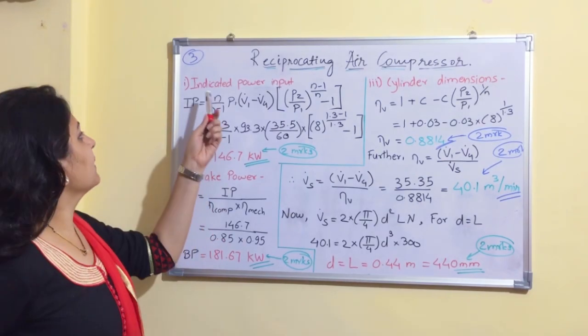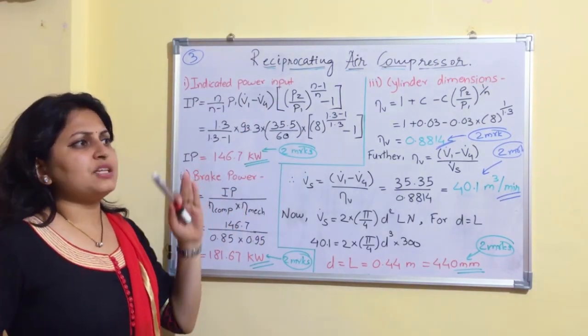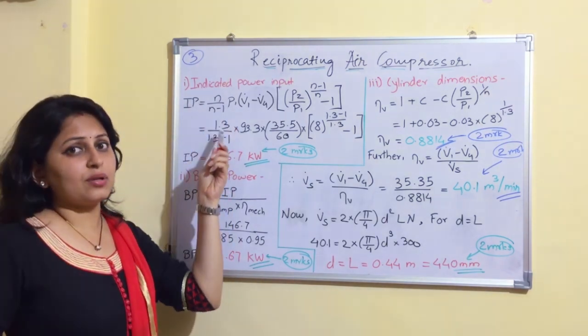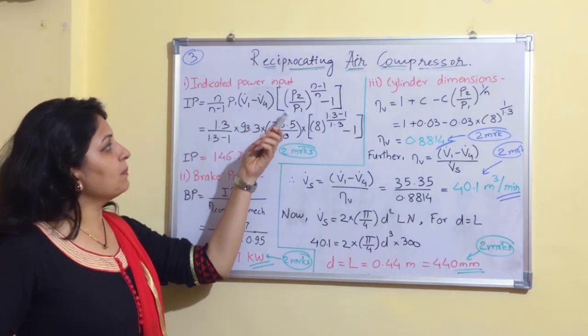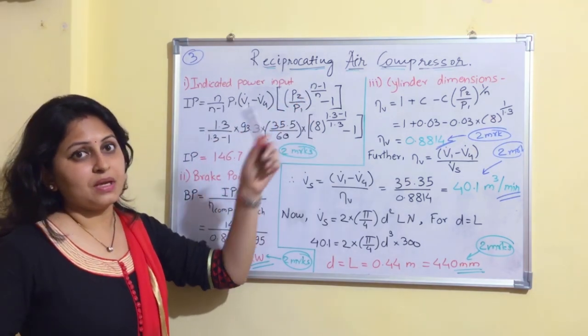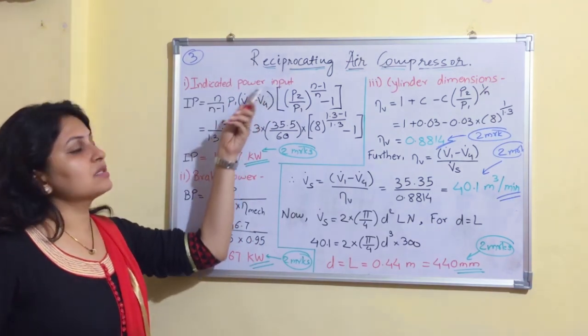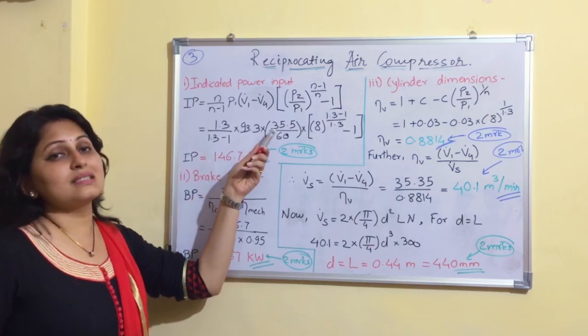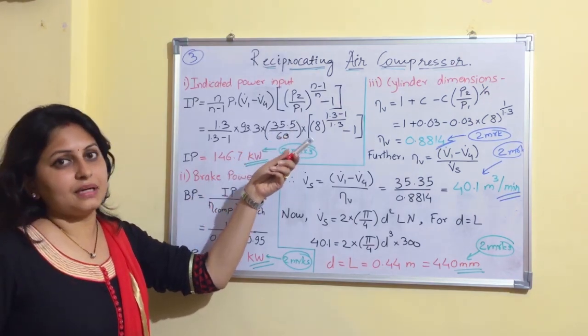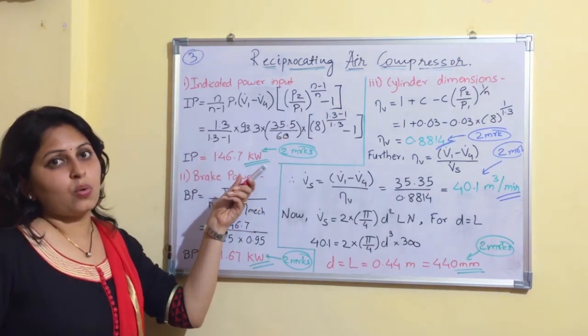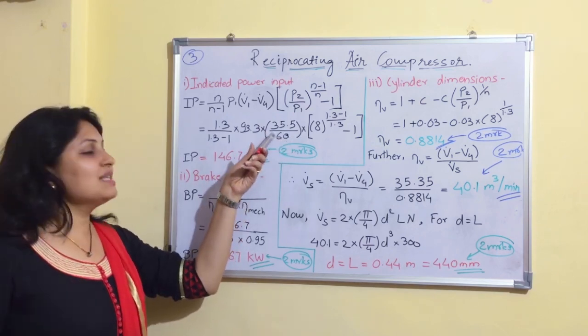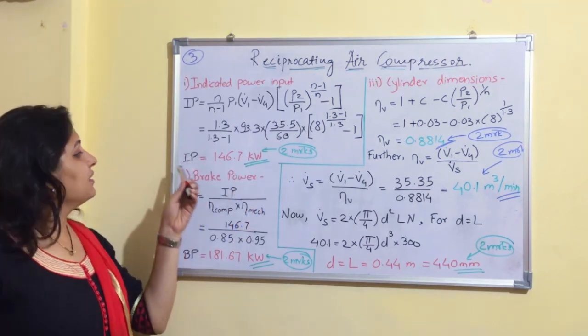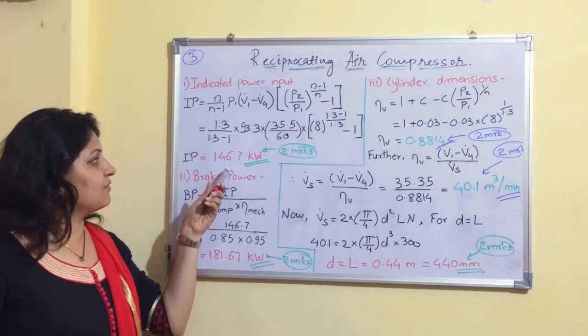Now let us find indicated power. With clearance included, the formula is: IP = [n/(n−1)] · P1 · (V1−V4) · [(P2/P1)^((n−1)/n) − 1]. Substituting (V1−V4) = 35.5/60 m³/s and the remaining values, we get IP = 146.7 kW.